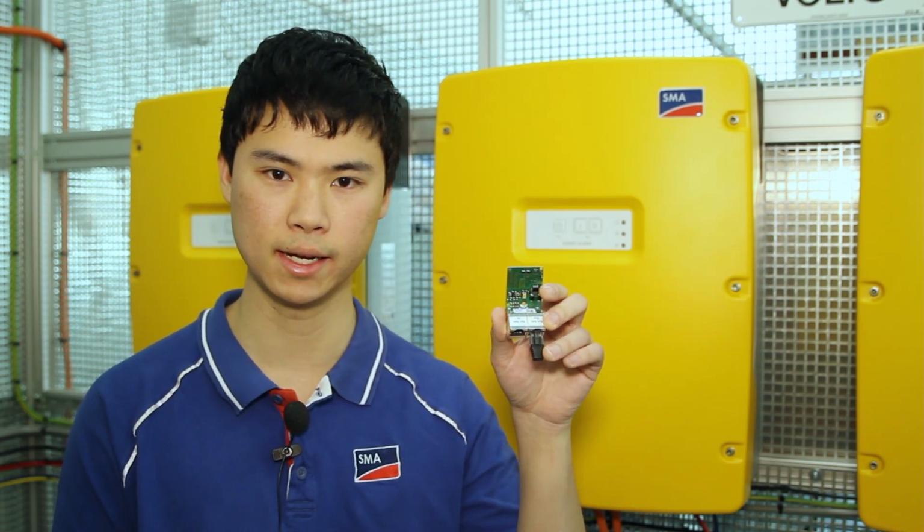There are three types of interface add-ons that you can retrofit with the Sunny Island 6.0H and 8.0H. The first add-on is the SI Syscan interface when using a multi-cluster box to allow communication between the master of the main cluster to all masters of all extension clusters, each cluster consisting of one master and two slaves.